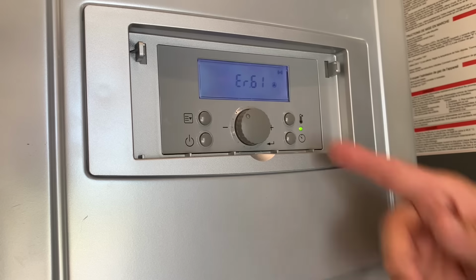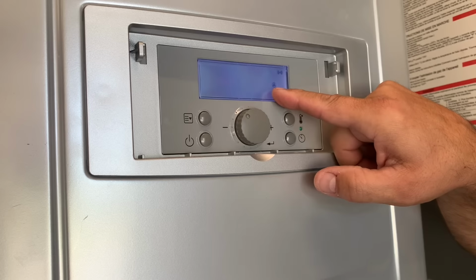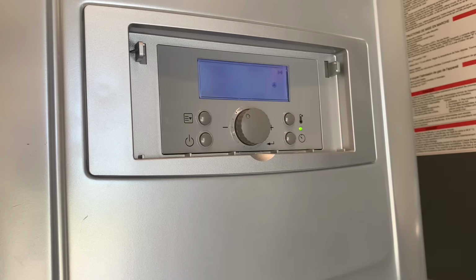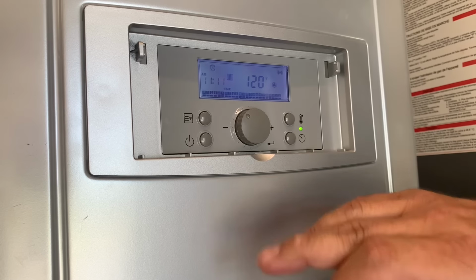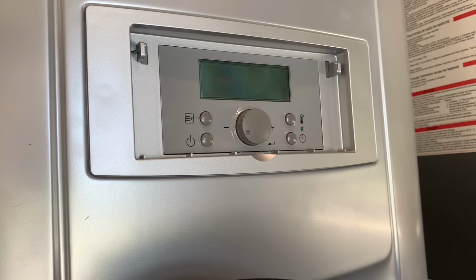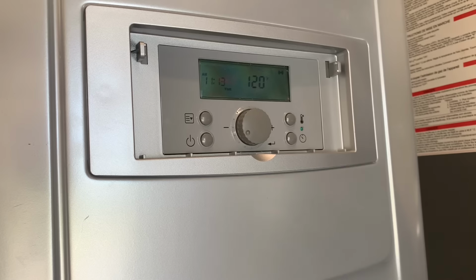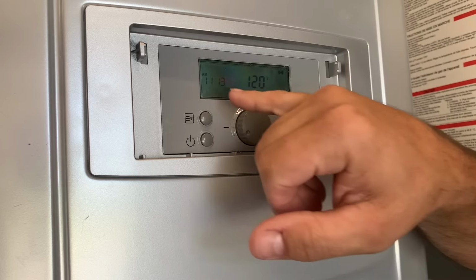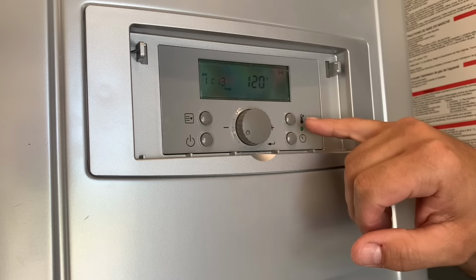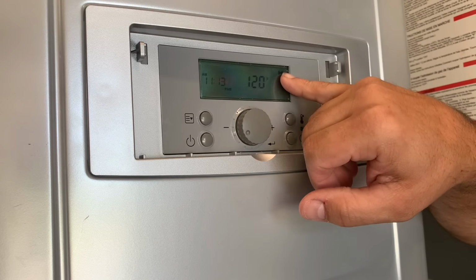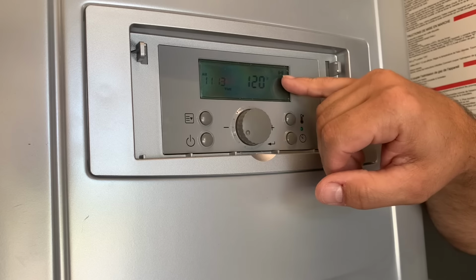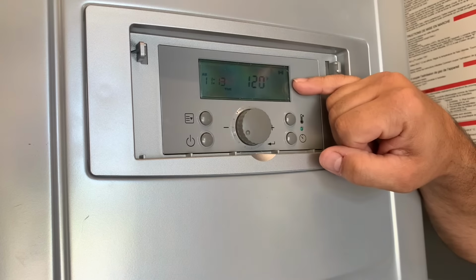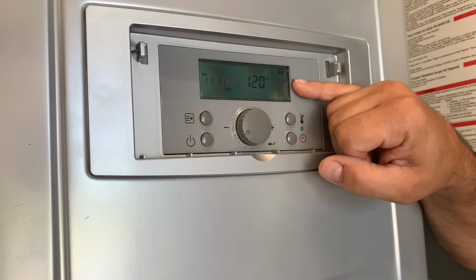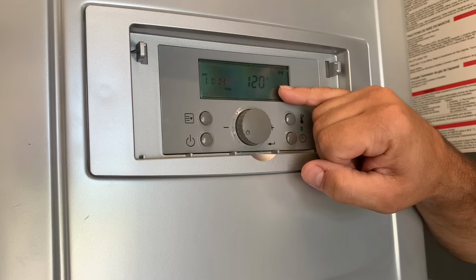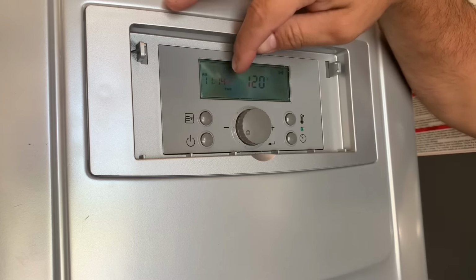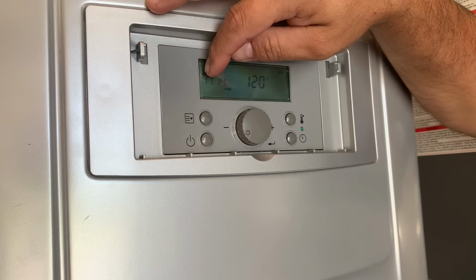And give you an error code 61 when the circulating pump comes on. This little triangle here says the circulating pump is kicked on. Error 61. We do not have any gas supplied to this unit. Unplug this and restart it. So this display will tell you almost everything when you're looking at it. It will tell you the time, it will tell you the day, temperature set point. This up here is a communication icon, so the unit is in a communicative state. Down here there's going to be a flame that'll kick on when the water heater is calling for some heat, and our triangle will light up when the circulating pump comes on.